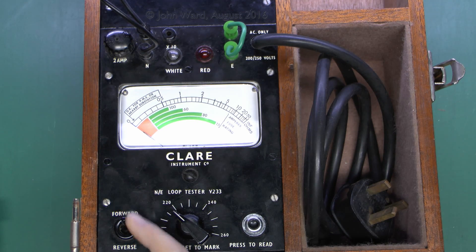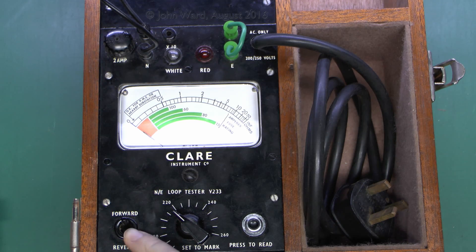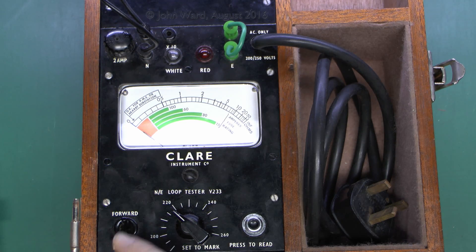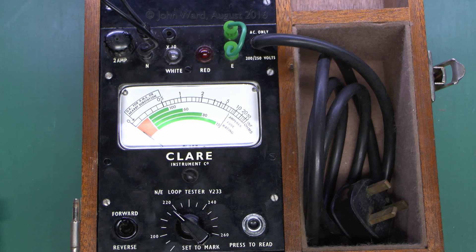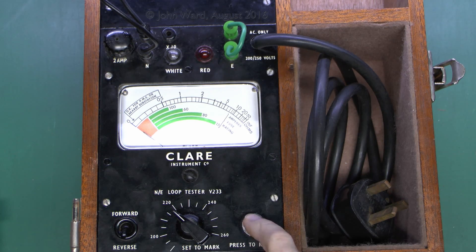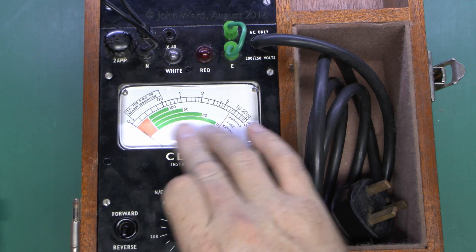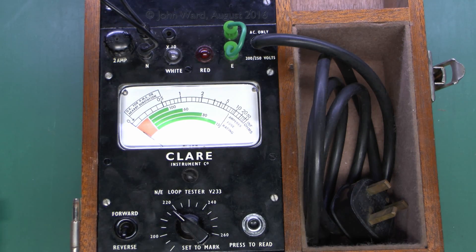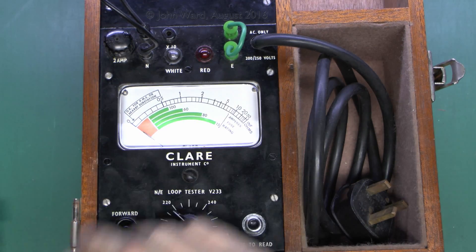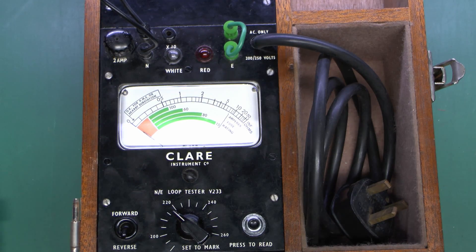And once you've done that you've got this forward and reverse, which is basically just changing the polarity of the test current. As this uses DC as the test current, you just put it in reverse, then you test again, and then you're just taking the average of the two readings. And again you have to work that out yourself, so a bit of maths required there.